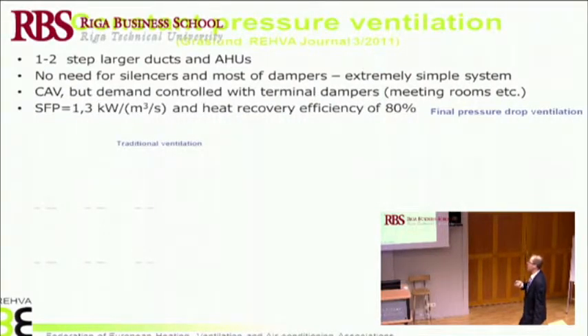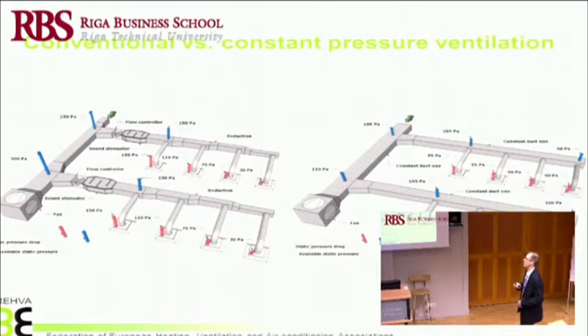And in such a case, if the pressure drop is very little, you can also use a constant volume system, maybe not in office rooms, but in meeting rooms, where there is a variable load. Indeed, you need controls, but all the other rooms can be a constant volume system, and you can go to very low specific fan power and indeed have high heat recovery efficiency because of these large air handling units. This is one sizing example of such a system.